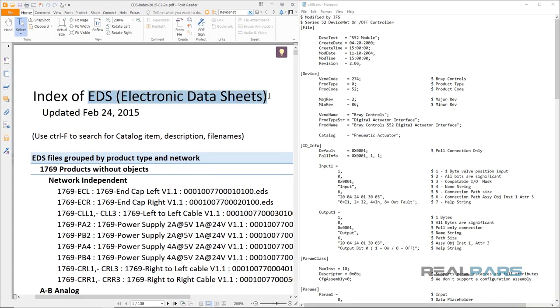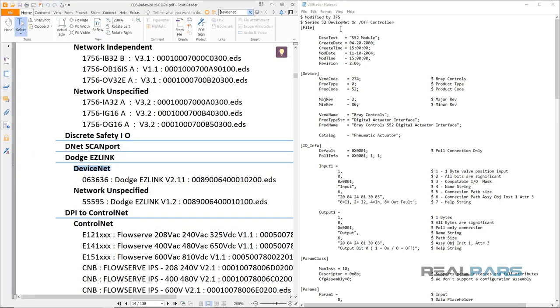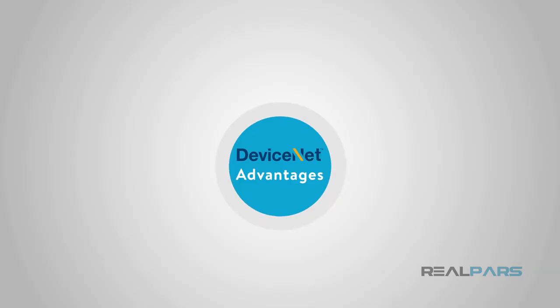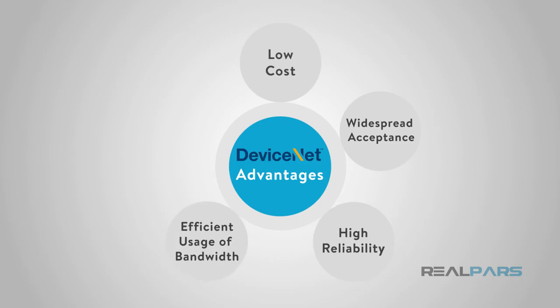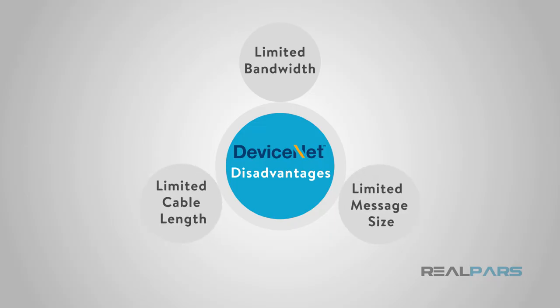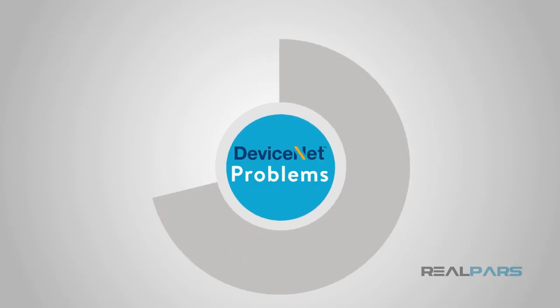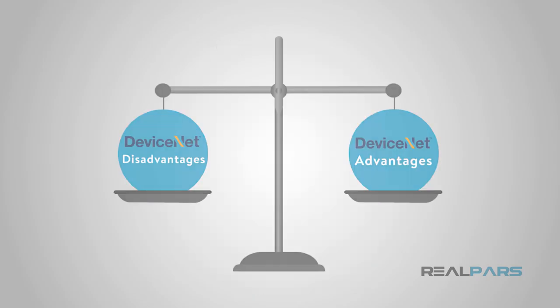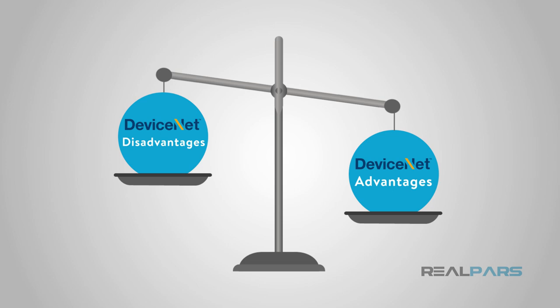DeviceNet uses Electronic Data Sheets, or EDS — simple text files that contain all the information to identify a device and assist in commissioning them onto the network. The advantages of DeviceNet are low cost, widespread acceptance, high reliability, efficient use of network bandwidth, and power available on the network. The disadvantages are limited bandwidth, limited message size, and maximum cable length. It is stated in many documents that 90% to 95% of all DeviceNet problems are one of two things: a cabling issue, or not having the correct EDS file registered in RSNetWorx for DeviceNet. This makes DeviceNet a great network when looking at the overall picture.